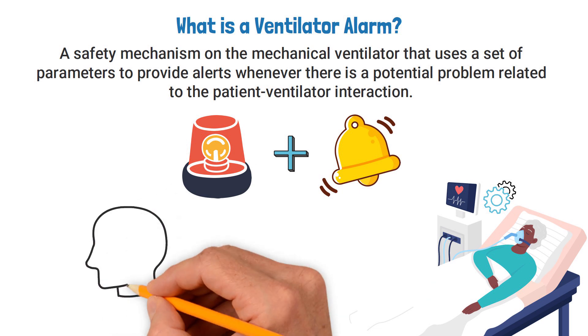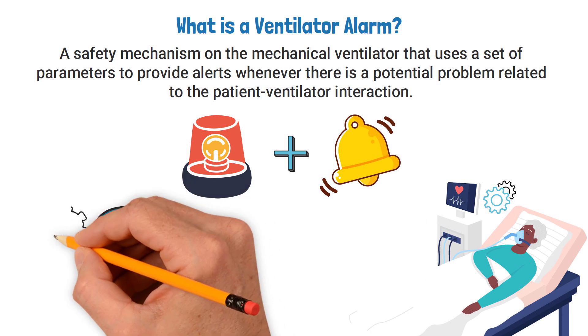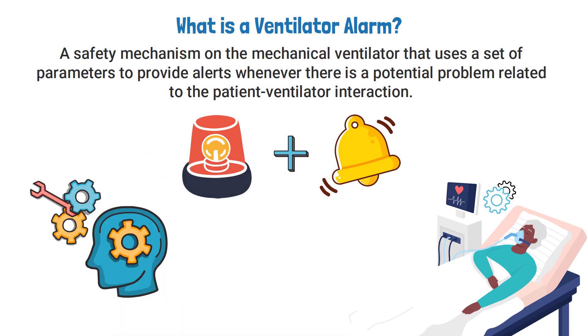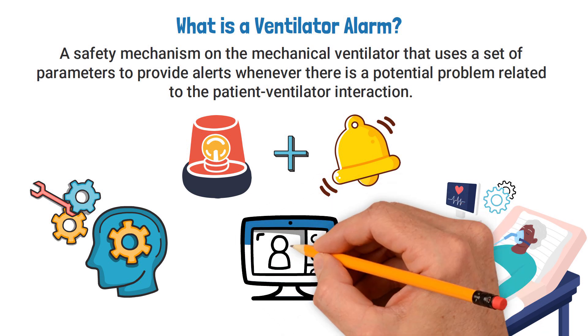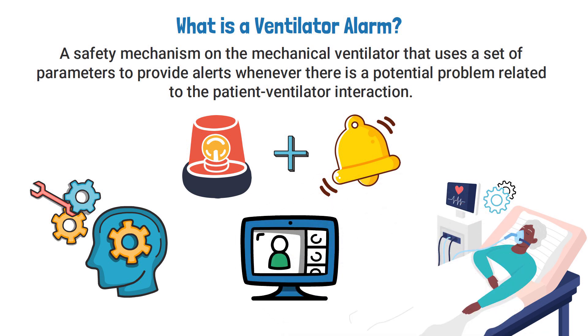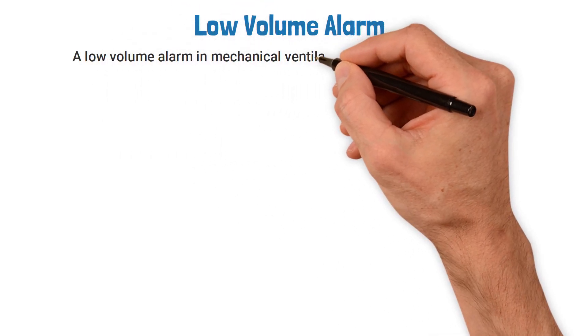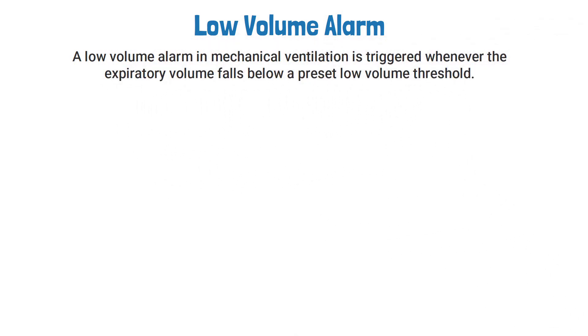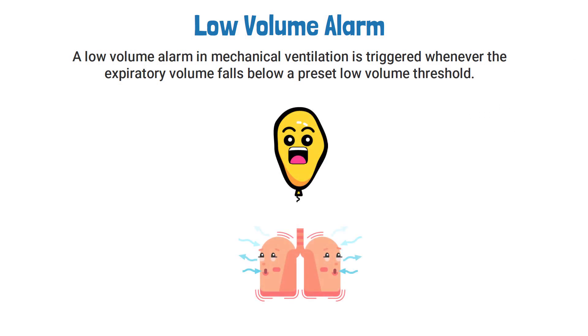In order to learn each of the different ventilator alarms, you must develop an understanding of the different ventilator modes and settings. For this video, we are specifically focusing on the low volume alarm. A low volume alarm in mechanical ventilation is triggered whenever the expiratory volume falls below a preset low volume threshold, which ensures the patient is receiving and exhaling a minimum tidal volume.